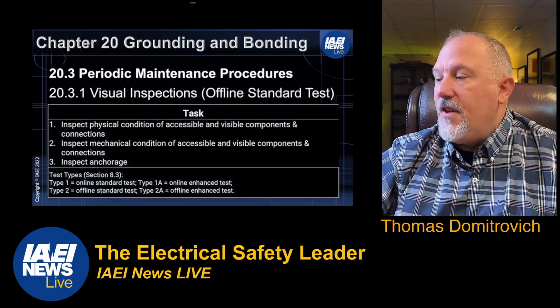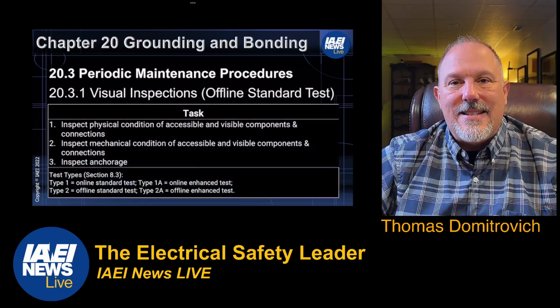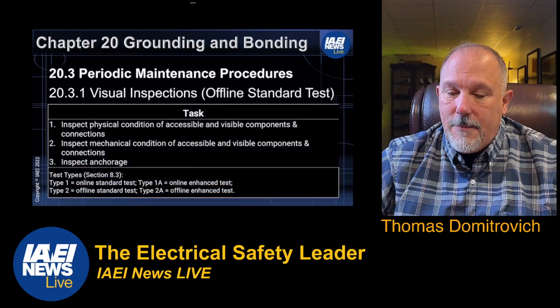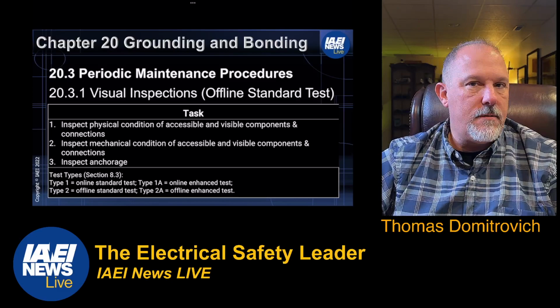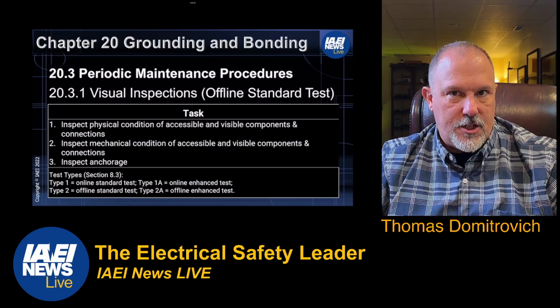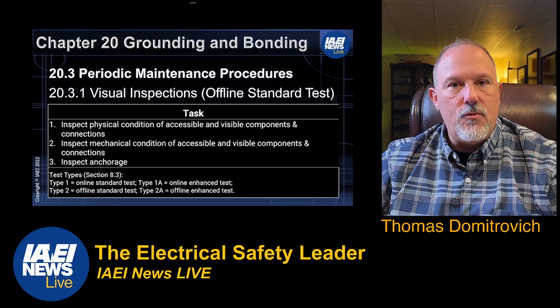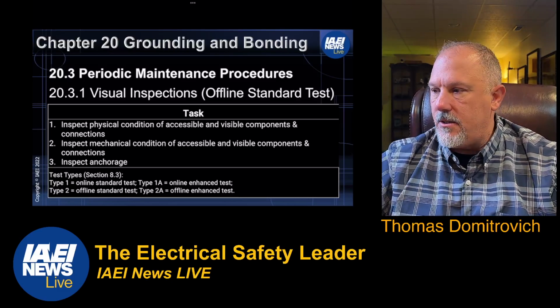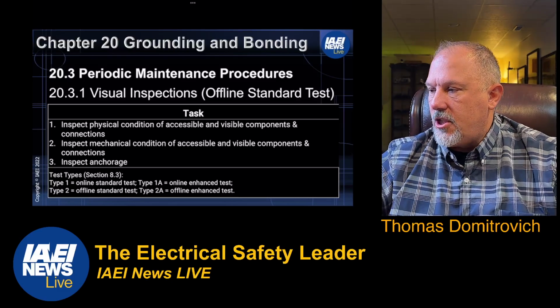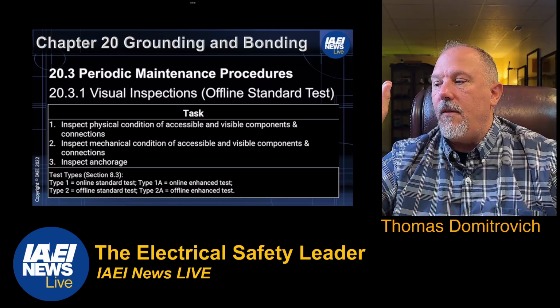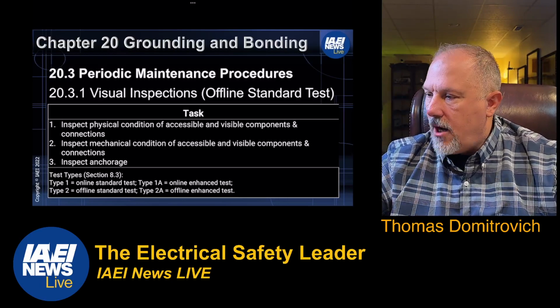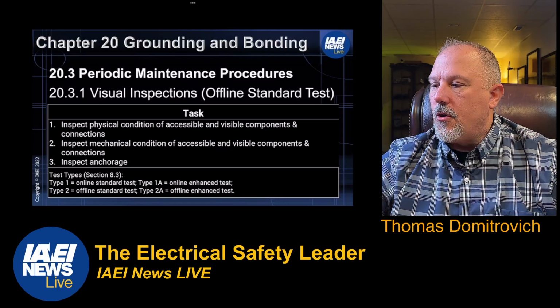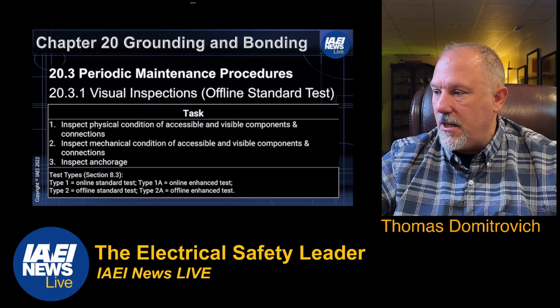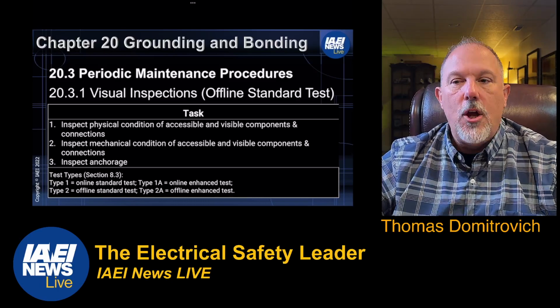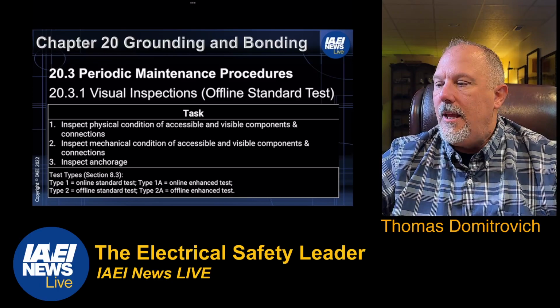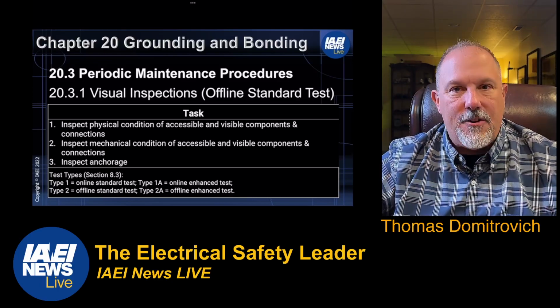All right, so visual inspections, offline standard tests. What does that mean? Offline is establishing an electrically safe work condition and performing these tests - you don't want to do these while energized. You're going to look at the physical condition of the accessible and visible components and connections, inspect the mechanical condition of the accessible and visible components and connections, and inspect any anchorage.